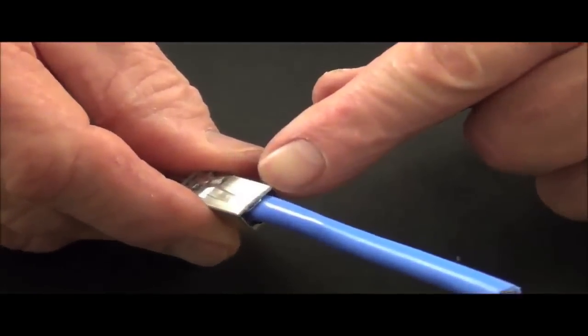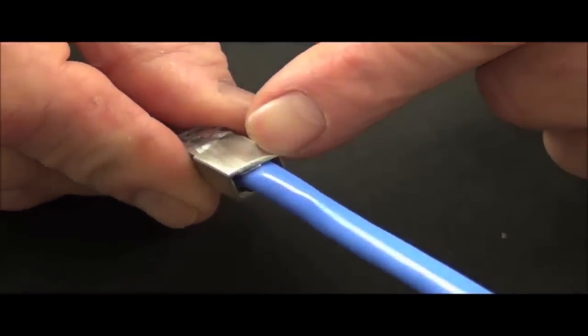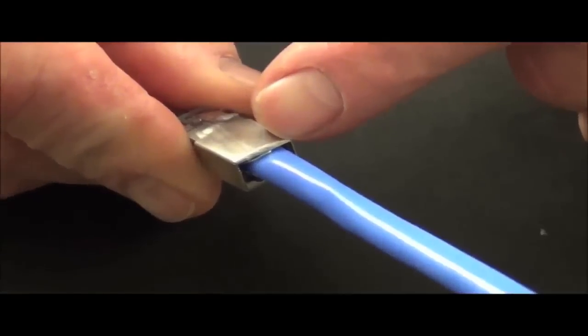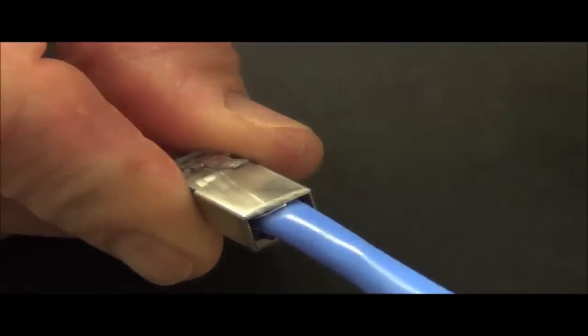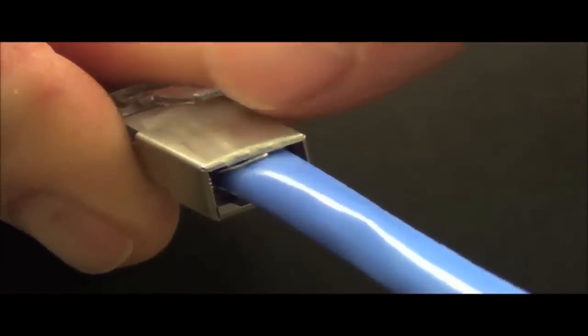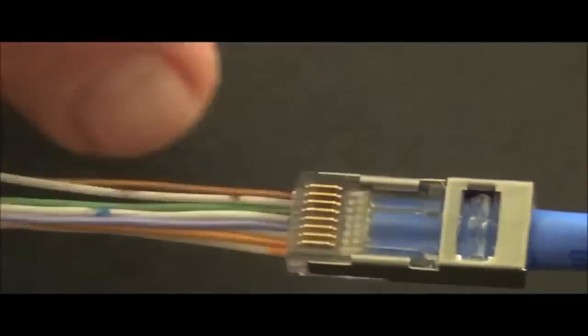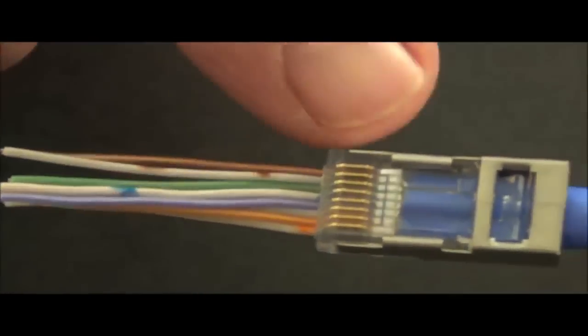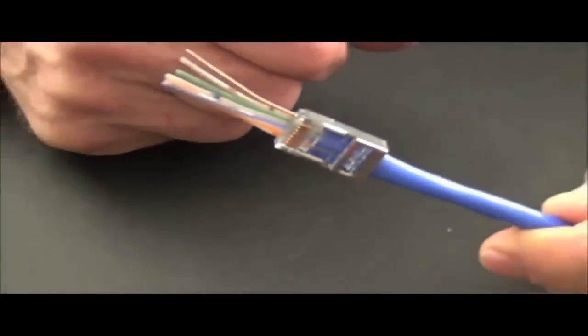Here's the back end. You can slightly see my ground wire, I looped it and coiled it around. It's sitting really nice on those springs, it's going to be a good ground. Am I going to meet Cat6? Yes I will, because my twist, see the end of the jacket, are right there where they belong at the back of the contacts. So here we go, Cat6 internal ground ready to be terminated.